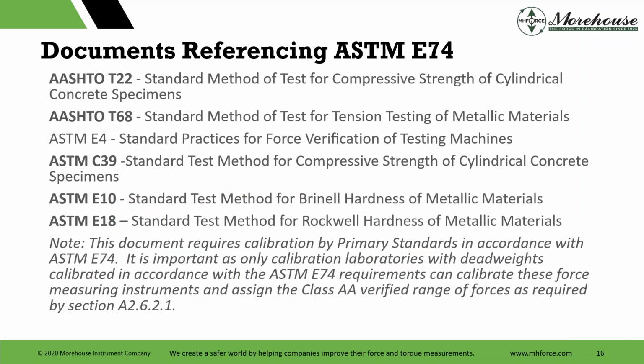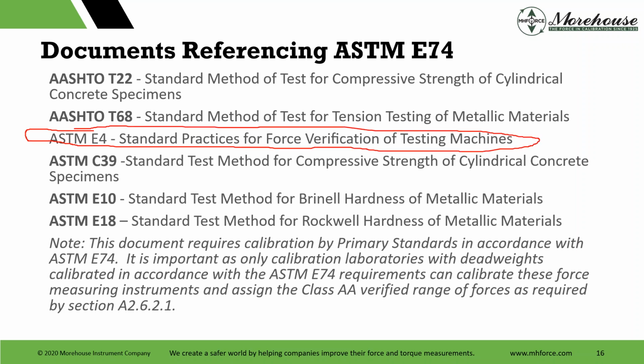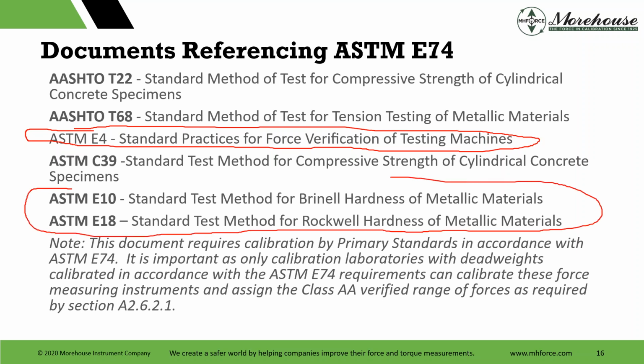So there are some documents that reference E74. If you're working to any of these standards, you're going to want to understand ASTM E74 as well. AASHTO T22, T68, ASTM E4, which I assume many people are doing. This is all over the world. The standard practice for force verification of testing machines. ASTM C39. Here are two that people don't get. A lot of our customer base, we're doing a lot more calibrations because people are referencing ASTM E10 and E18, which make a call out for E74.